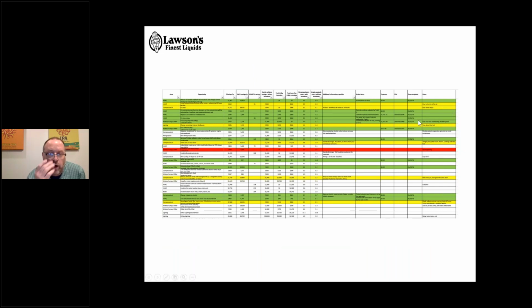Here's how we prioritized things. I know it's a lot to take in on this webinar, but as we prioritized, we really looked at high energy recovery and low cost first, with a short ROI. We had a lot of ideas, like turning down the compressor by 10 PSI to save money, or turning our boiler pressure down—do we really need the boiler running at 100 PSI when it's throttled down to 25 PSI at the brew house?